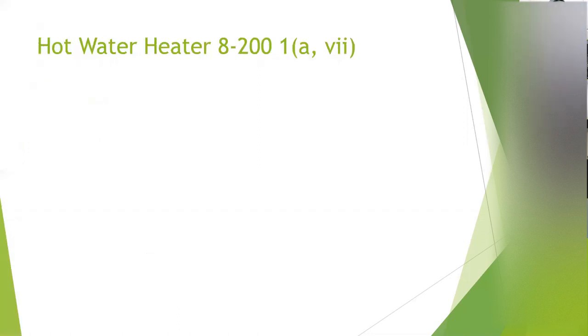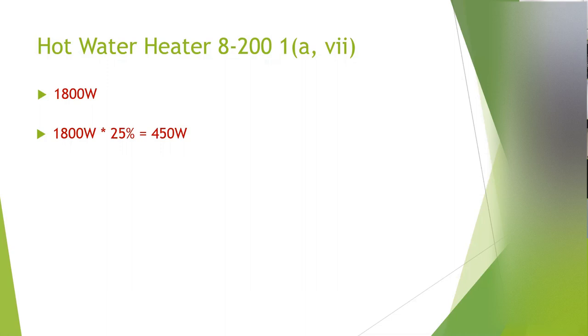Now the hot water heater. It falls under other loads. This is not a tankless hot water heater — since it didn't specify tankless, we assume tank. So it is taken at 25%. That gives us 450 watts to apply to the service calculation.